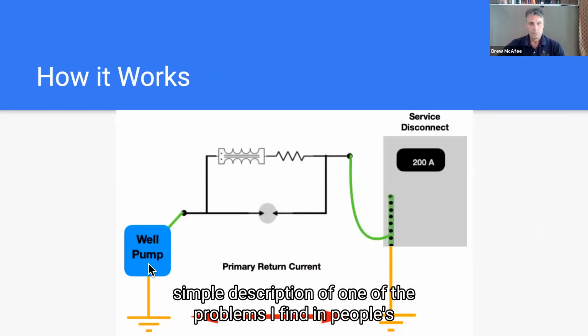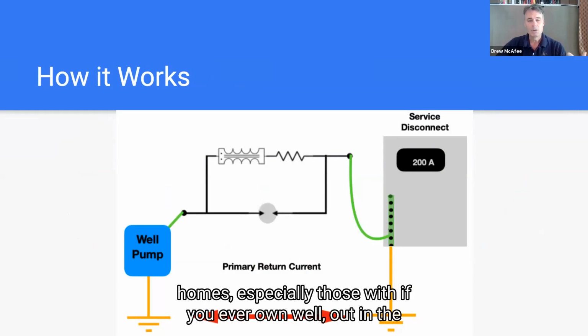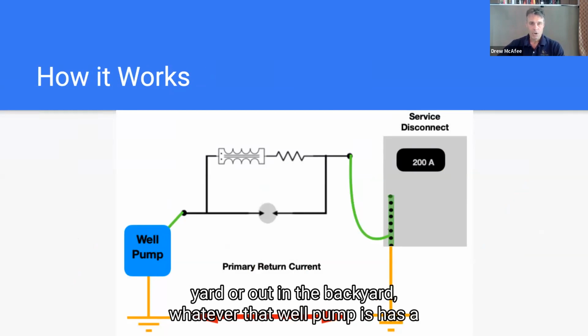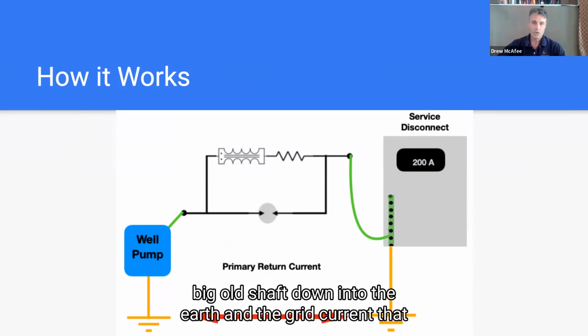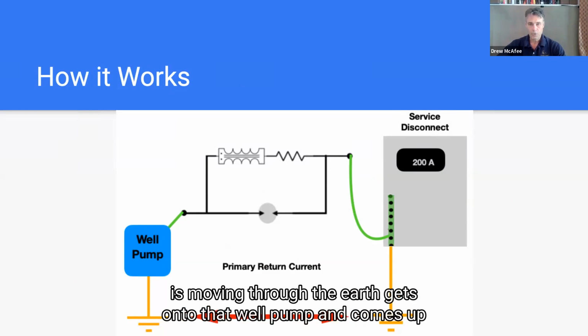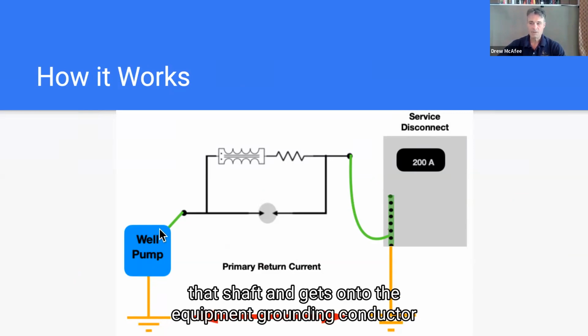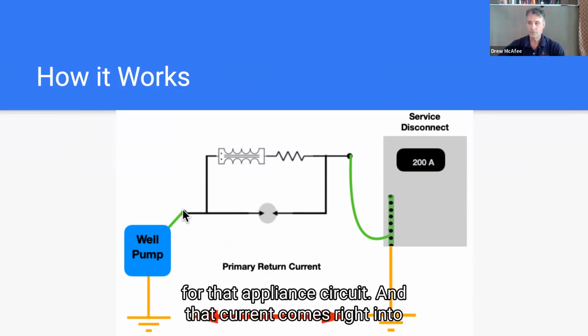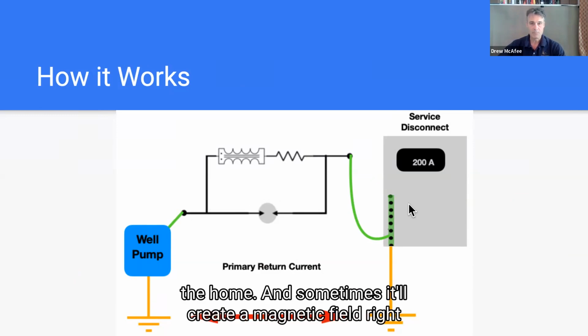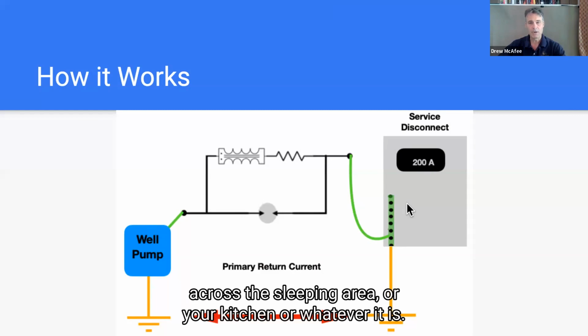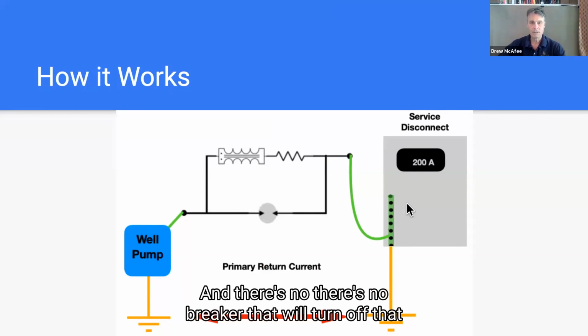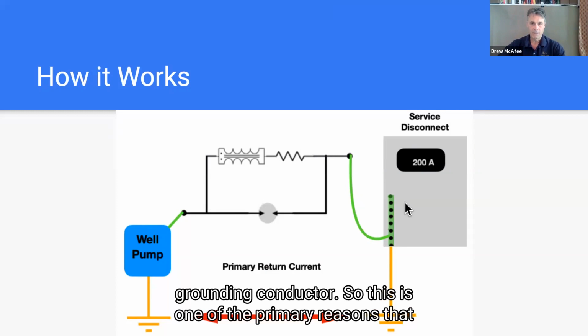Here's a very simple description of one of the problems I find in people's homes, especially those with your own well out in the yard. That well pump has a big old shaft down into the earth, and the grid current that is moving through the earth gets onto that well pump and comes up that shaft and gets onto the equipment grounding conductor for that appliance circuit. And that current comes right into the home. Sometimes it'll create a magnetic field right across the sleeping area or your kitchen or whatever it is. And there's no breaker that'll turn off that grounding conductor.